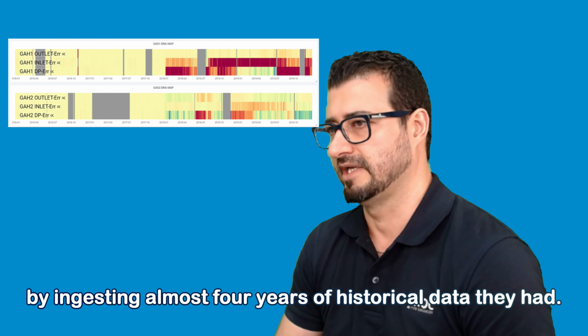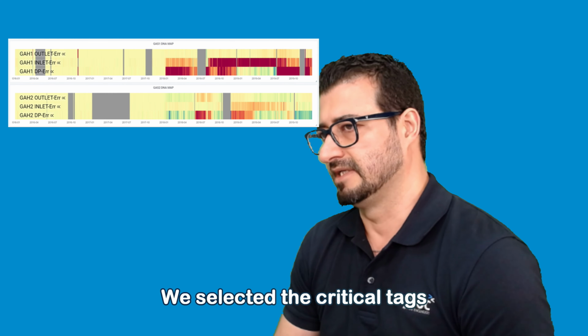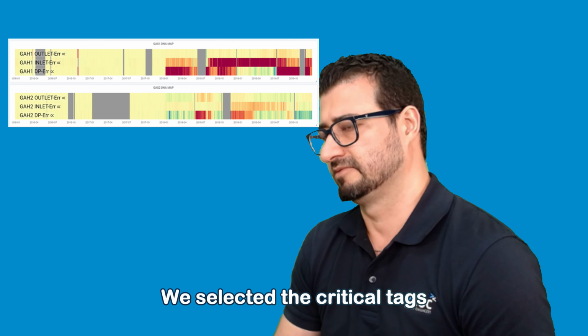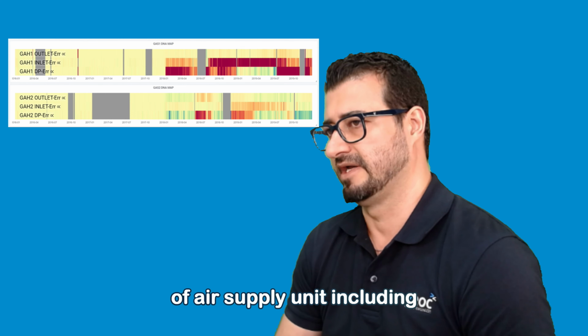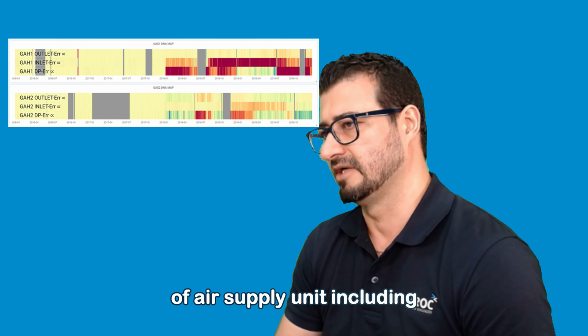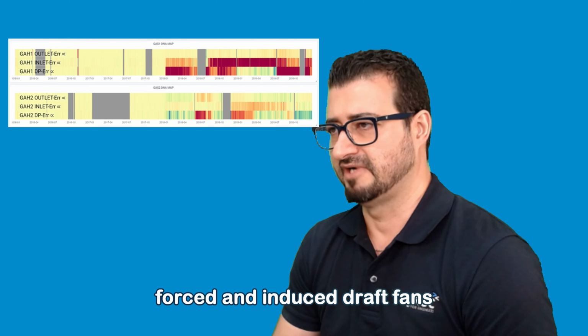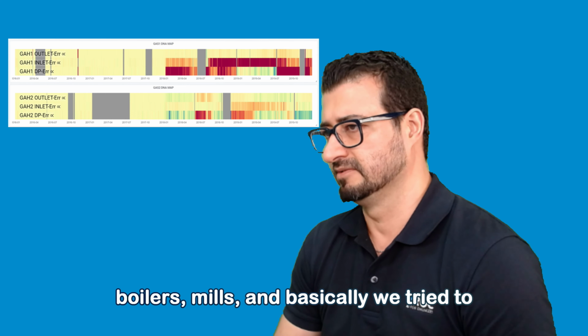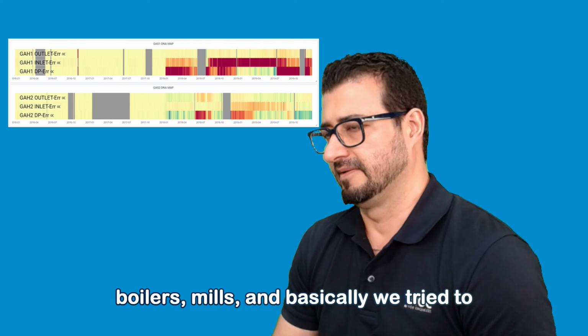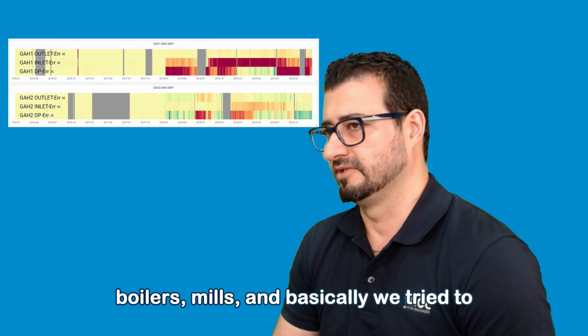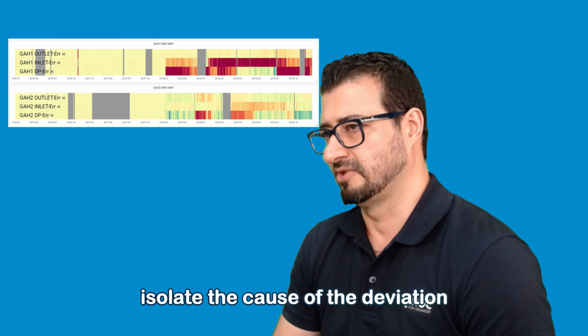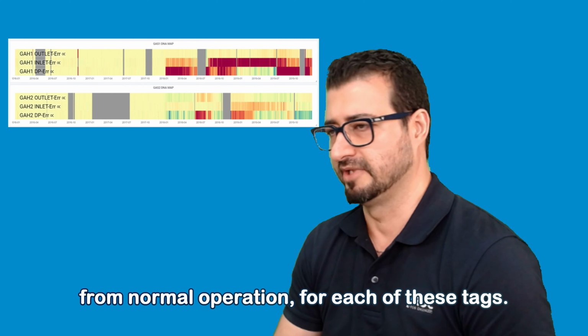historical data they had. We selected the critical tags of the air supply units, including forced and induced draft fans, boilers, mills, and we tried to isolate the cause of the deviation from normal operation for each of these tags.